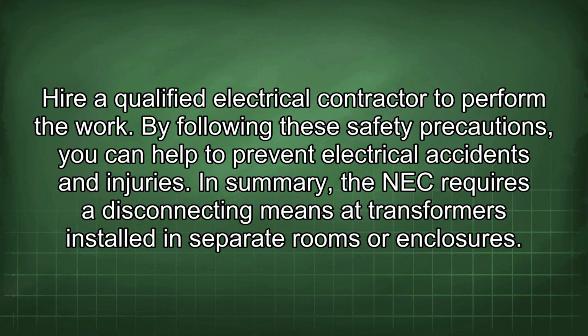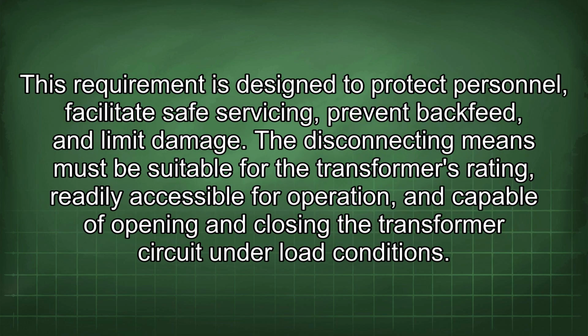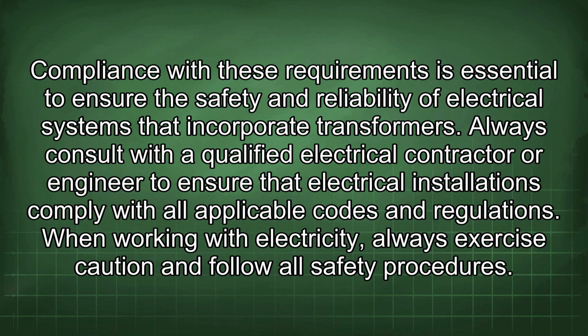In summary, the NEC requires a disconnecting means at transformers installed in separate rooms or enclosures. This requirement is designed to protect personnel, facilitate safe servicing, prevent backfeed, and limit damage. The disconnecting means must be suitable for the transformer's rating, readily accessible for operation, and capable of opening and closing the transformer circuit under load conditions. Compliance with these requirements is essential to ensure the safety and reliability of electrical systems that incorporate transformers.